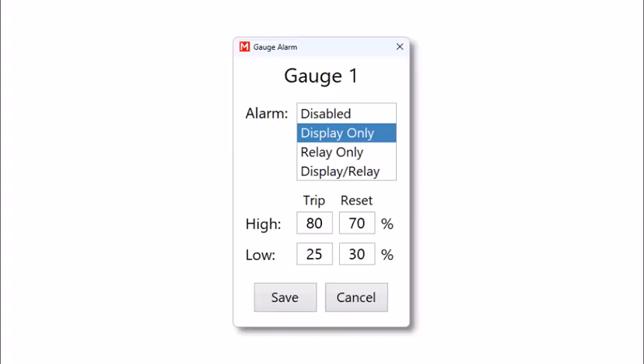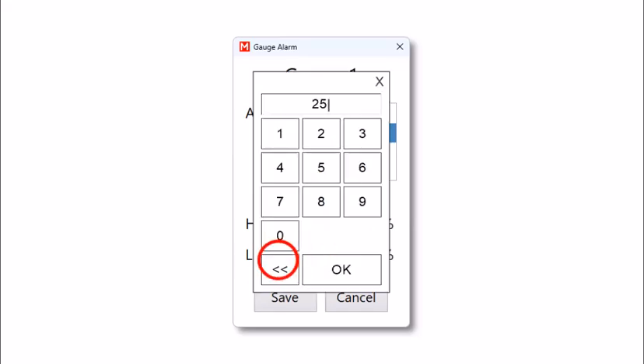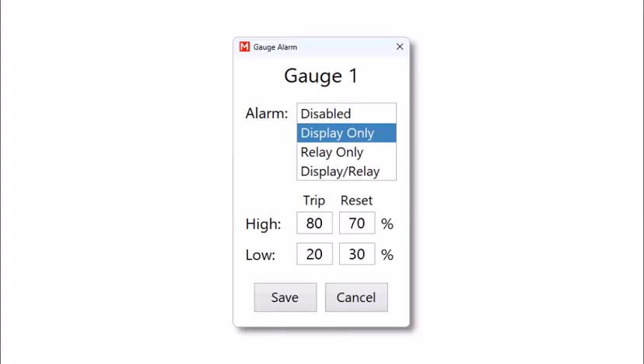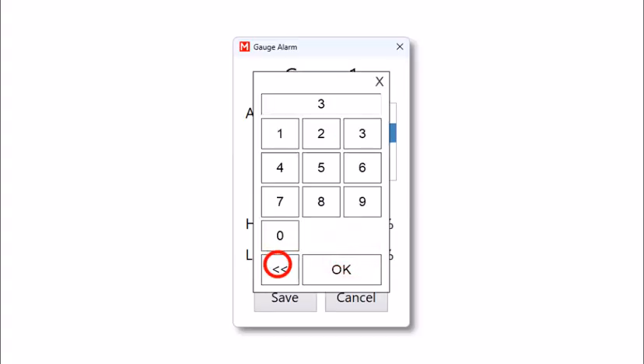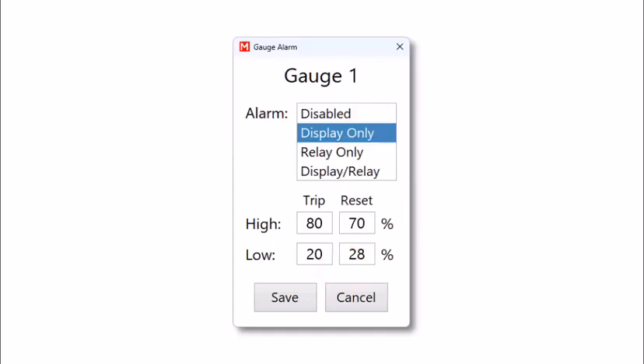The low alarm is set up the same way. Let's change our low alarm to trigger when the bin is 20% full. We'll change that the same way we did for the high level. We clicked on the low trip field, entered 20 on the keypad, then hit OK. Our low alarm is going to reset when we reach the reset percent level. Let's change our reset level to 28%. Then hit OK. Now, our low alarm will be active until our bin level exceeds 28%. Let's go back to the main screen to see that in action.